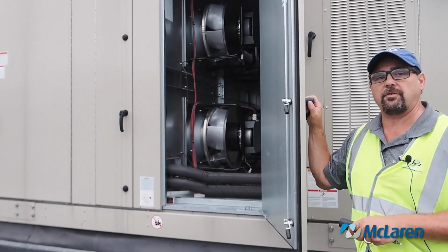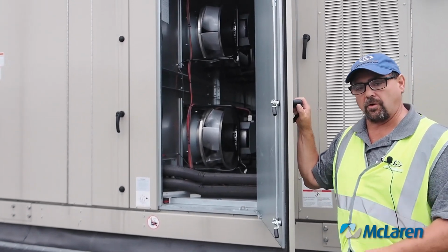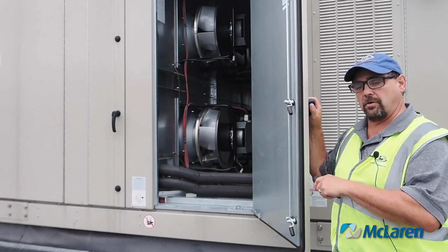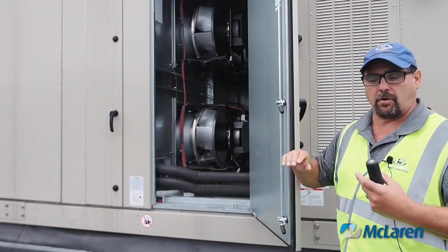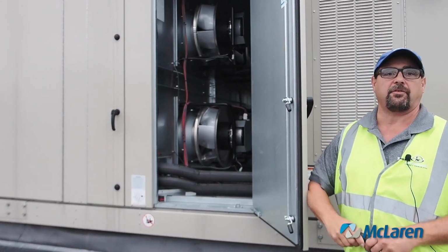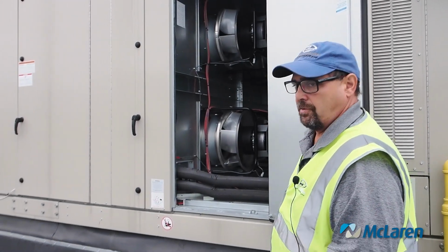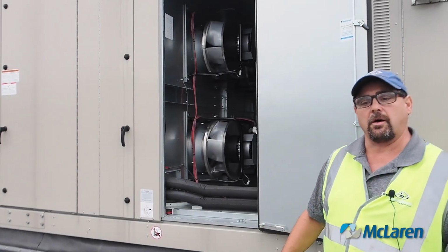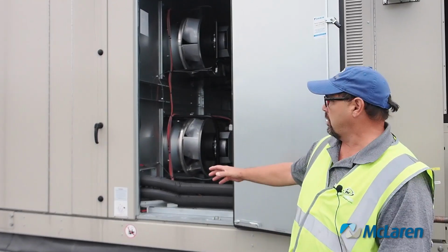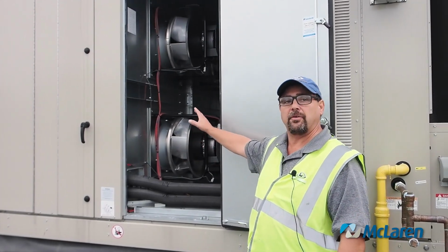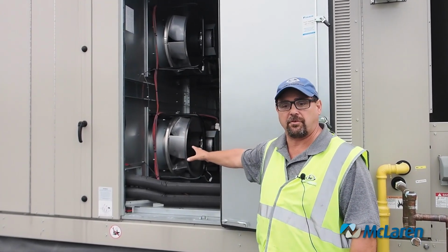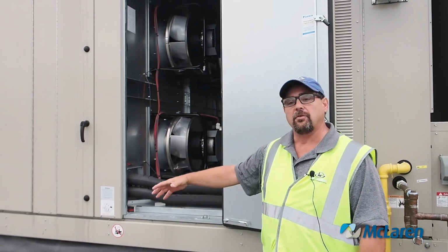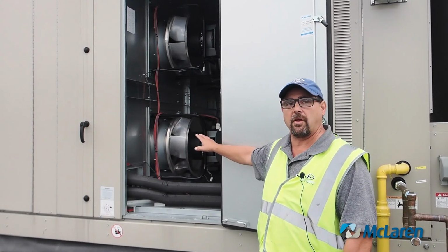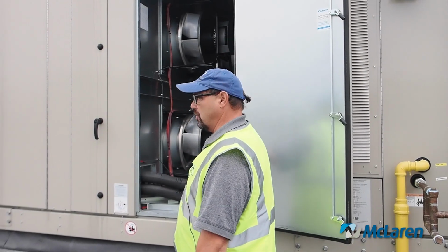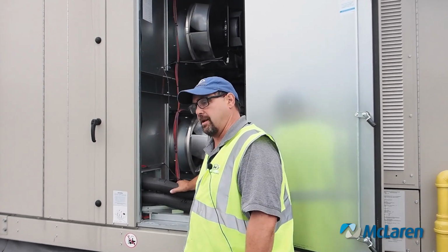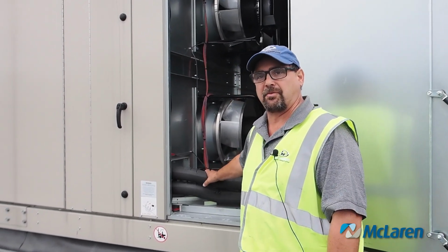No maintenance on these. No grease, nothing to oil, no belts. If they do fail, you replace the whole thing, the wheel and the whole motor, because it is a programmed device on the back of that motor. If you do have to replace a motor and there's a time frame you have to wait for it, you take this out, get a piece of sheet metal and block off the section that the bad fan is in, so you can try to keep your motors running and keep up the CFM as high as it could as needed. They do get shipped with a block off plate, but 99.9% of the times I've seen it get thrown out as scrap.